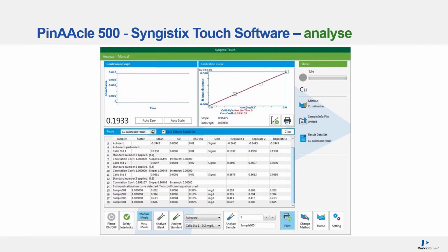So turning your flame on or off, checking that all safety interlocks are satisfied. You can choose to run in both manual and automated mode. So if you have an autosampler connected, you can use that as well. In manual mode, you will be able to select Analyze Blank, Analyze Standards. You can choose from a list of your standards in the drop-down list right next to it.